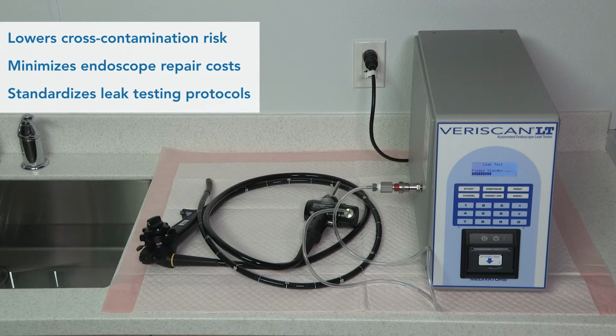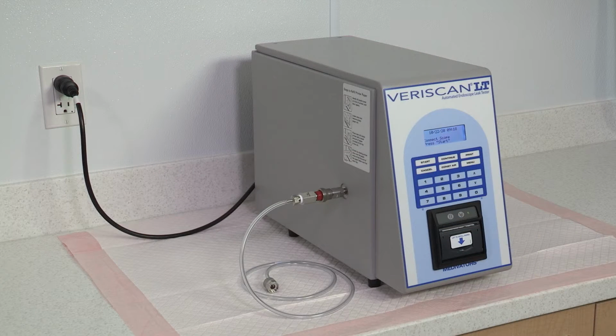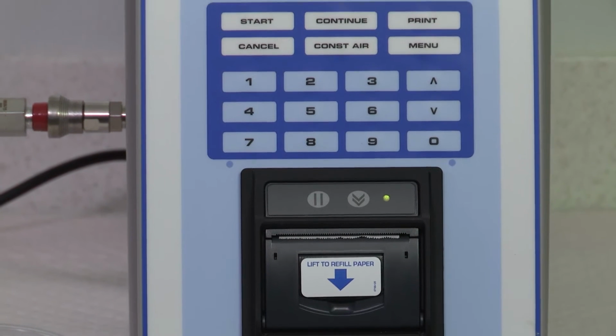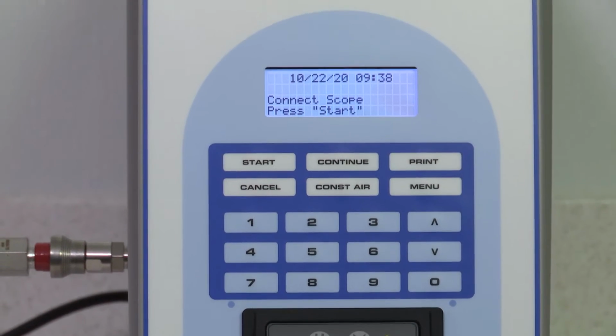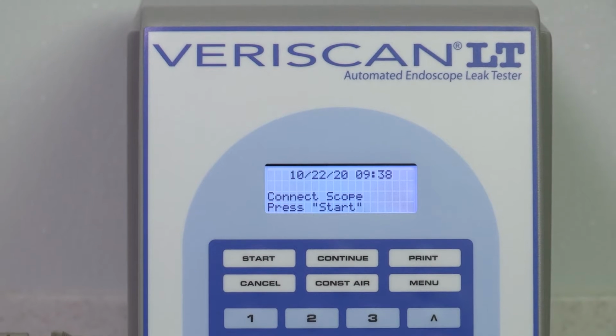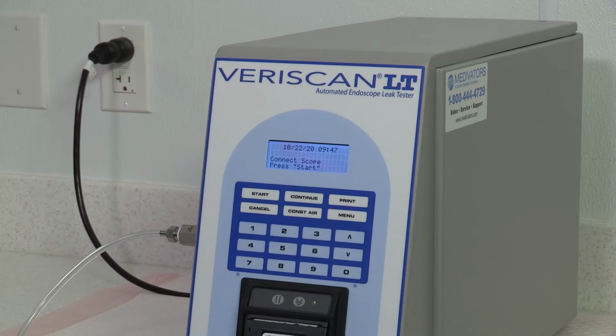The VERISCAN Leak Tester's dry leak test method detects endoscope leaks on the interior and exterior of an endoscope. If an endoscope leak is detected, the endoscope should immediately follow your written procedure on how to clean and disinfect, take out of service, and send in for repair.